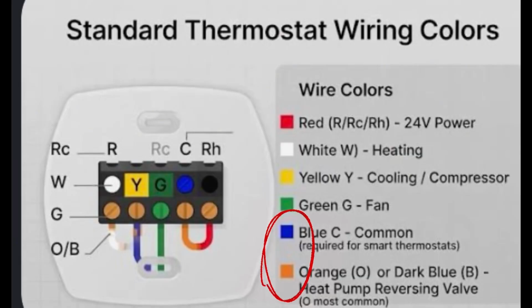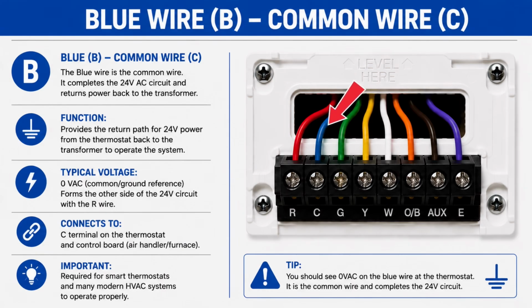These last two wires have two separate important functions. The blue wire is typically the common side of the 24-volt transformer circuit. It provides the return path for 24 volts back to the HVAC control board. This wire powers smart and digital thermostats continuously. It completes the 24-volt circuit, usually connecting to the C terminal at the thermostat and HVAC control board. It does not normally turn on heating or cooling components by itself.